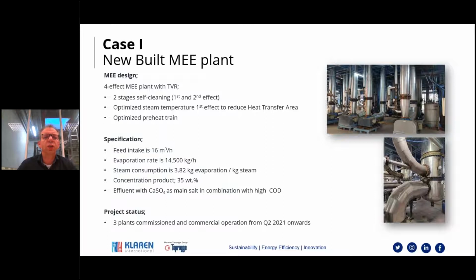We have also chosen to equip 2 stages of this multi-effect evaporator plant with self-cleaning. The reason for this is that the assignment we had was to design a really optimized plant in terms of heat transfer area, to make a compact plant. And the only way you can do that is in fact increasing the temperature difference, which normally would give fouling issues. But since we have 2 stages with self-cleaning, we know that this will keep the heat exchanger surfaces clean, so we could do that. So with the same amount of heat transfer area, in fact, we can do a higher evaporation rate. The third point to mention is that we have carefully looked at where we can still regain energy from waste heat sources. I will show you that later. So we have made an optimized preheat train.